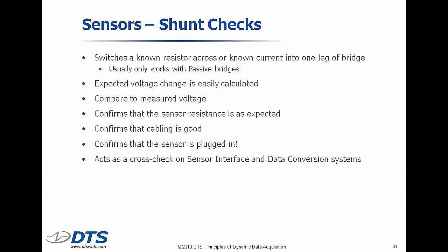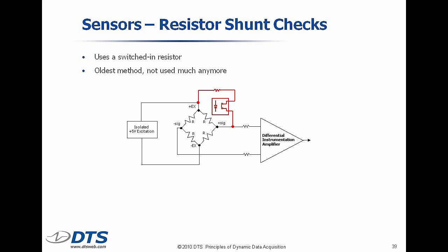I'm sure some of you in the room remember shunt checks, or maybe even use them today. When you wire up a transducer, mostly bridges, Wheatstone bridges, sometimes we switch in a resistor across the bridge, and what that does is it has the effect of simulating an applied load to the transducer by offsetting the bridge just like a real load would do. So it has the benefit that shunt tests can be used to cross-check the setup, and they can be used to tell you, gee, is the sensor plugged in? Is the cable good? Is the transducer likely working okay or not?